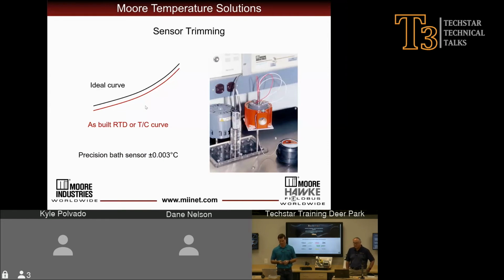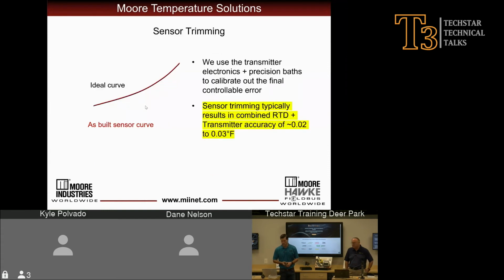And we know that the precision bath sensor temperature is within that 0.003 degree of uncertainty. Now, what this does for us is it actually yields a trimming of the RTD or sensor accuracy of 0.02 to 0.03 degrees Fahrenheit. So this gives us a lot more accurate of the temperature measurement. And this is another way that we can calibrate the final controllable error out of our transmitter and sensor combination.